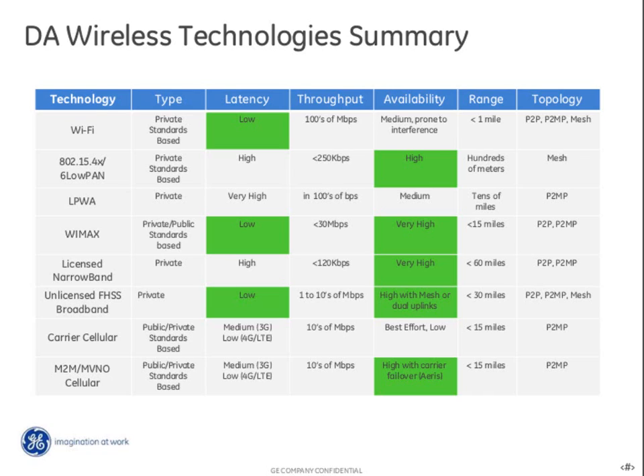802.15.4 or 6-LoWPAN, a mix of technologies, they have higher latencies, usually in the hundreds of milliseconds, and throughput is somewhere between 250 kilobits per second. I've seen recently some as high as 600 kilobits per second. And they are highly available just because of the nature of the mesh network. If you lose one section, you go back to another one. And range is usually within hundreds of meters.